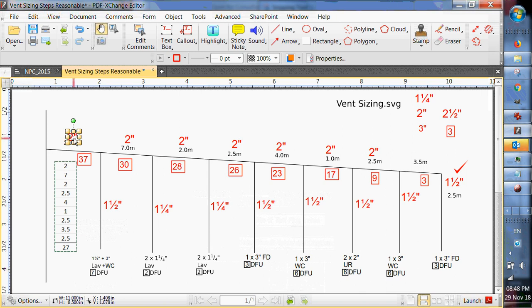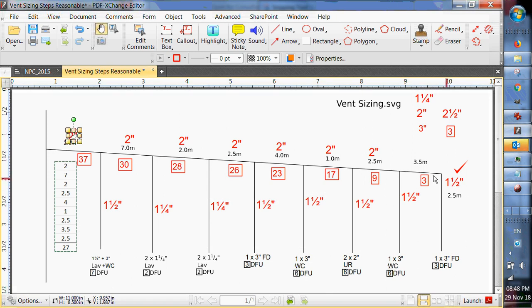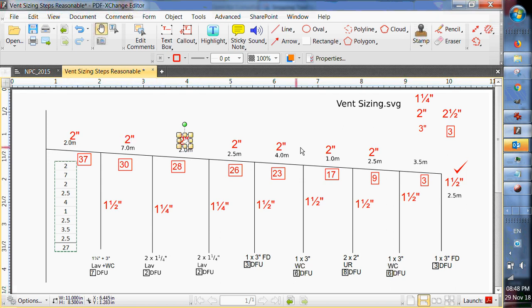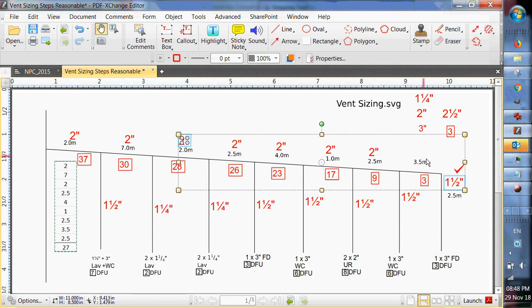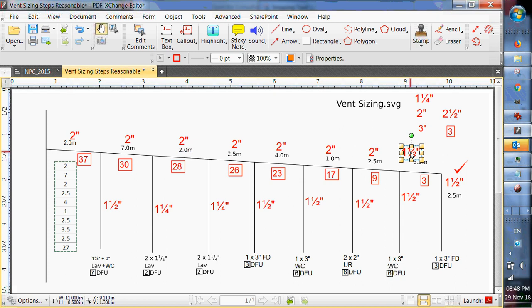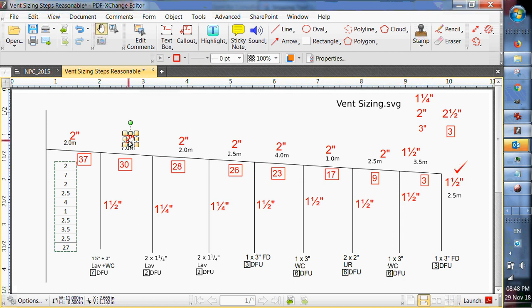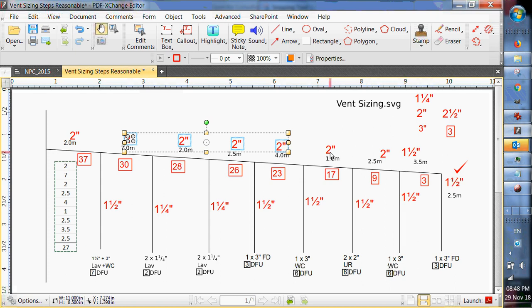In the interest of making things simpler, quite often we'll leave stuff off of drawings because you can figure out by looking at the drawing what the sizes are. So right from here, this two inch goes up to here. This could be a three inch depending on what's coming up here. But right up to here, we're two inch. So we don't really need any of these except for where it changes from inch and a half. So I'm going to put the inch and a half there and the two inch there. So that's telling us that we're inch and a half on this side of the tee. We're two inch on this side. The rest of them I can just delete. Because I've got two inch at each end, so this is all two inch.